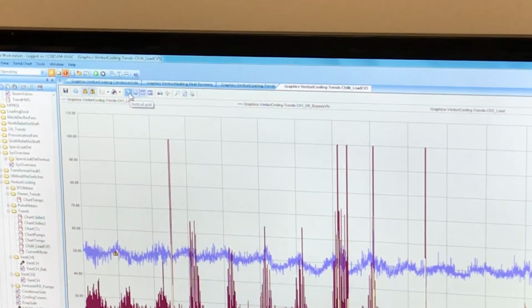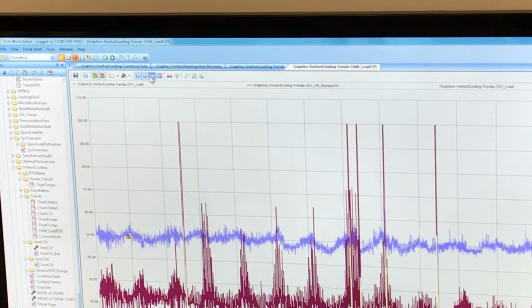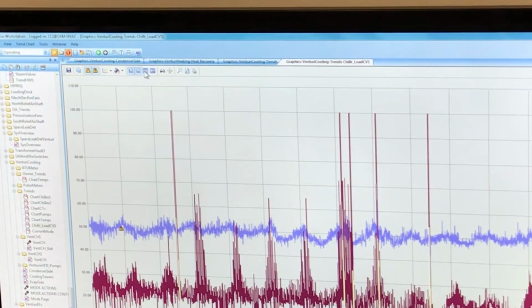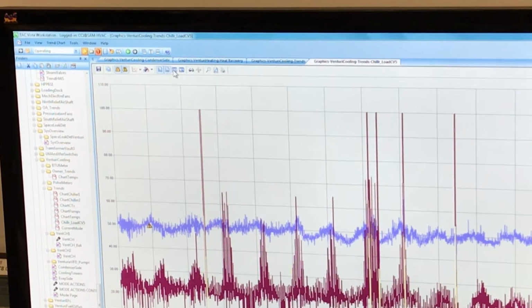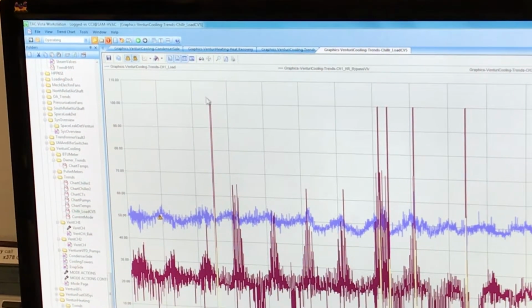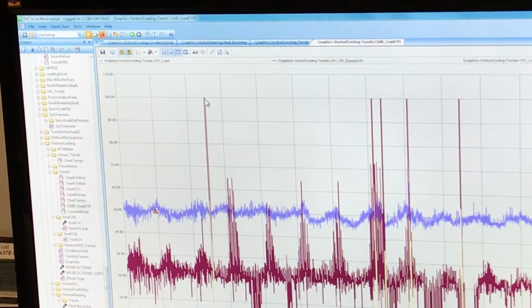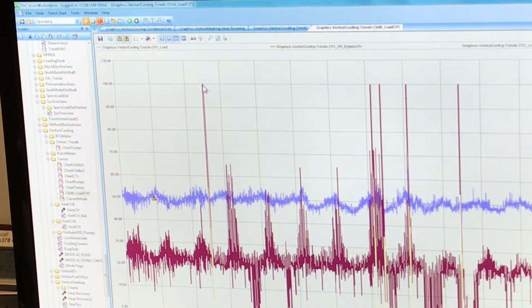he said you can probably run all the way down to 10 because of a high entering condenser water temperature. Yeah, because you get too much of a differential between the evaporator and the condenser. When the condenser goes way up there, you get almost identical delta P between the two. So he's saying that probably 30.